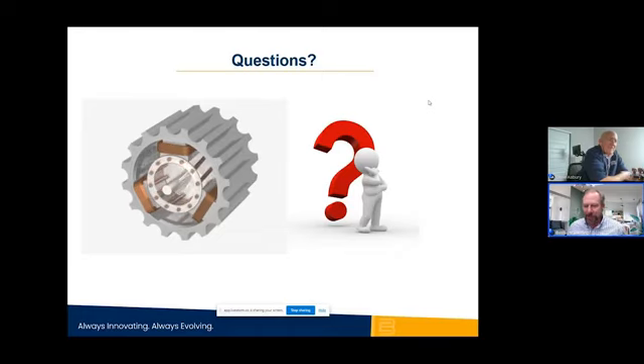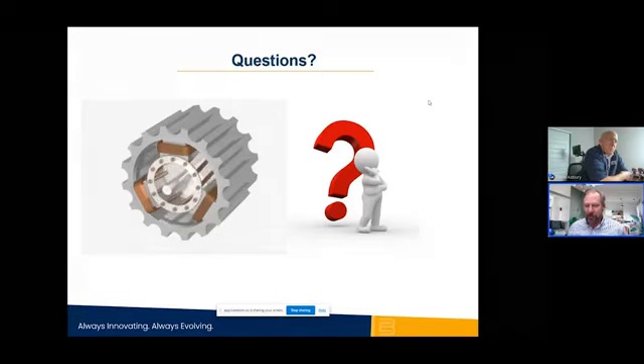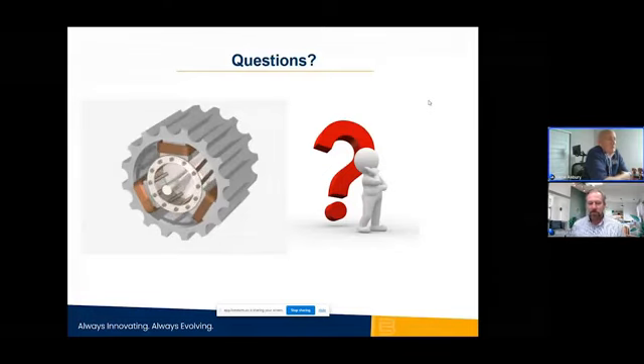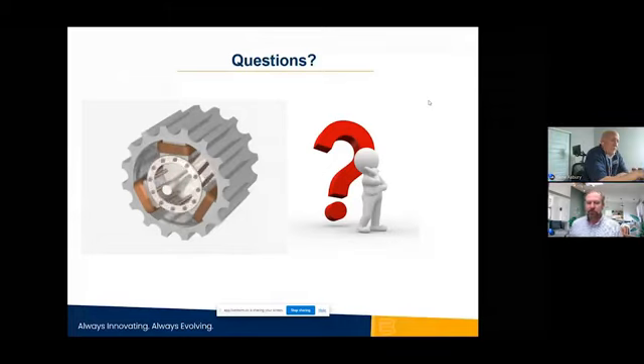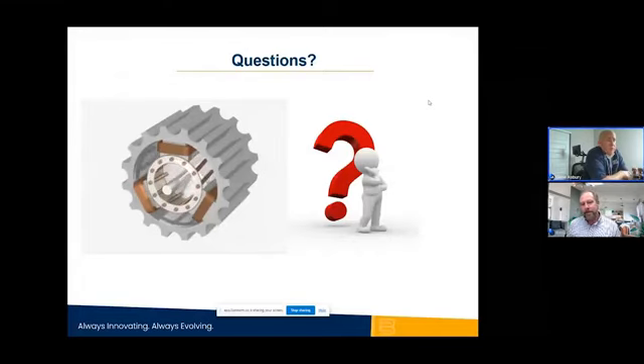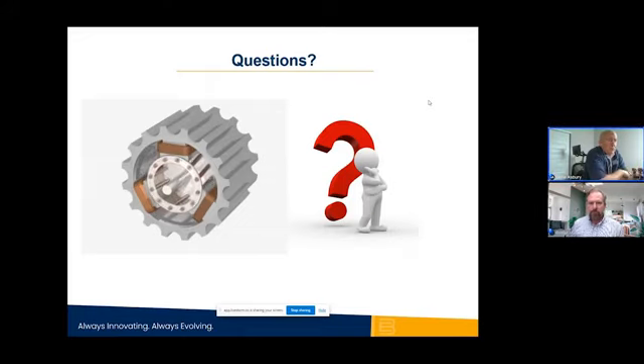All right, we got another one. Is there any Basler technical system to monitor field current and voltage in the brushless systems? I mean, for the rotating part of the system. That's a good question. I'm assuming he's talking about going into the main field of the motor, and if they give us a shunt out there or something, we could do it, but I've never seen one. All we can do is monitor the motor output and the exciter field. On some large brushless generators, I think Westinghouse used to put a shunt out there so you could monitor the main field also.